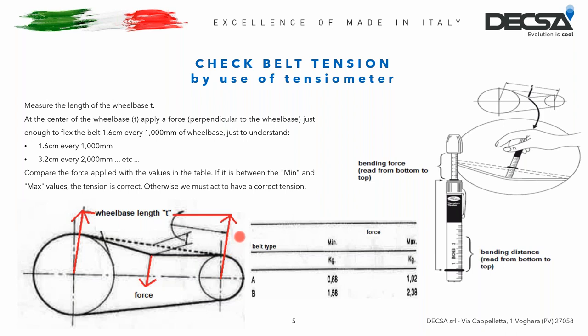At the end of the operation, the tensiometer must give a value between the minimum and maximum; otherwise the belt tension must be changed. I indicate the values for type A and type B belts because they are the most commonly installed models on our units. The belt model is followed by a number indicating its length. These data are very important — if you want to buy new belts from us, we need them to provide you with the correct ones. The best way is always to send us a photo of the nameplate applied on the unit.